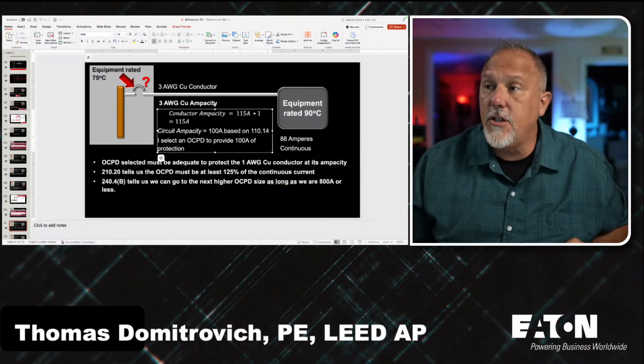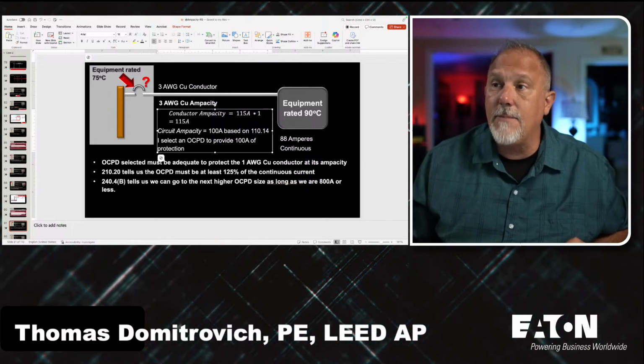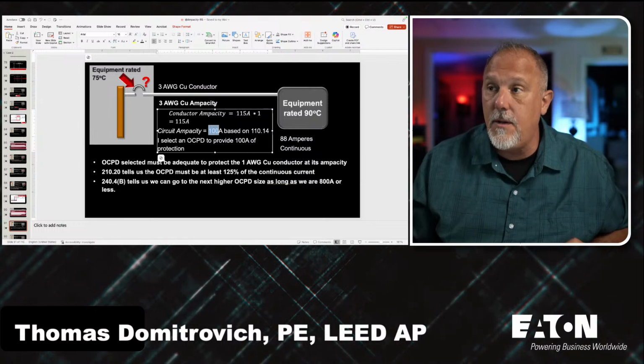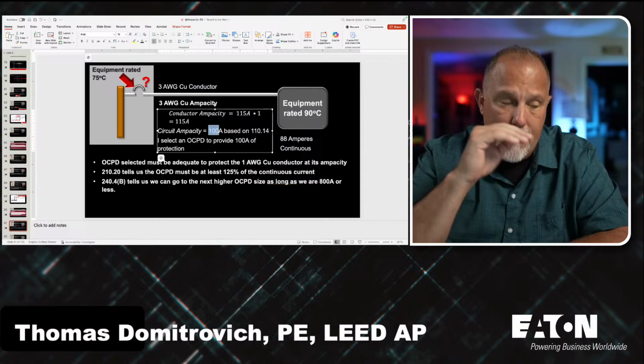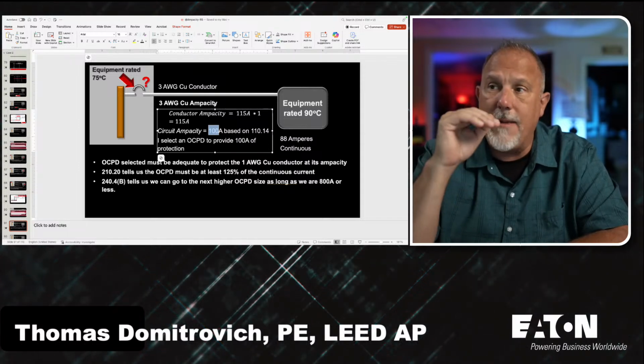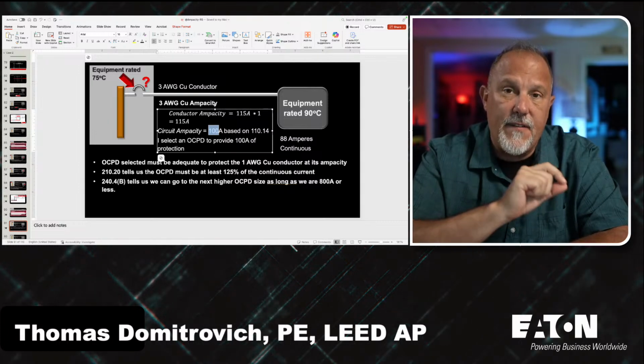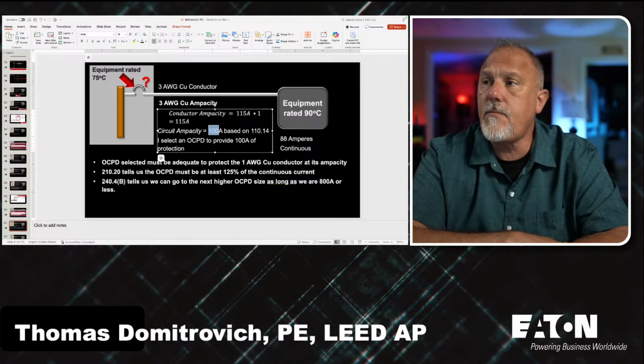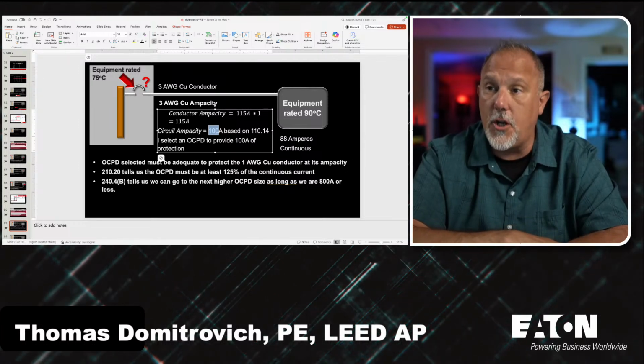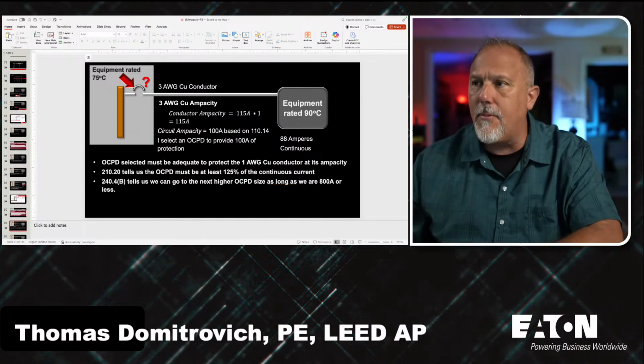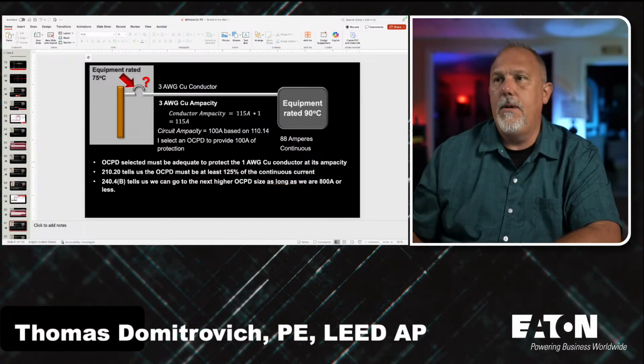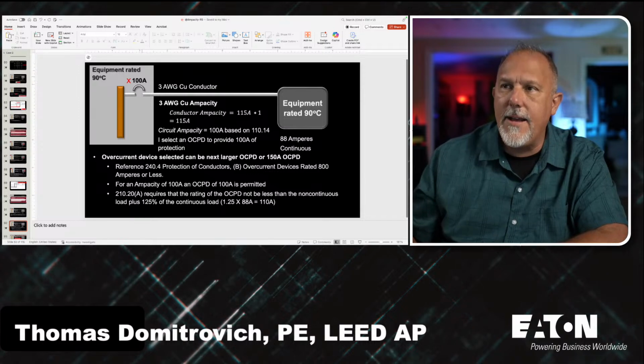I select an overcurrent protective device to provide 100 amps of protection because of that maximum requirement. Remember, my circuit ampacity, which is limited based upon the 75-degree C equipment, can't go greater than 100 amps on that number 3 conductor. So I pick a 100 amp breaker. So now I know I have a 100 amp breaker.